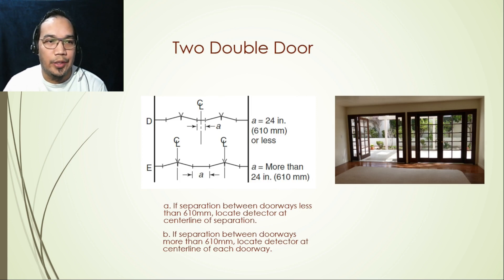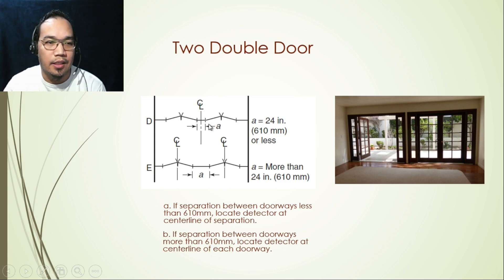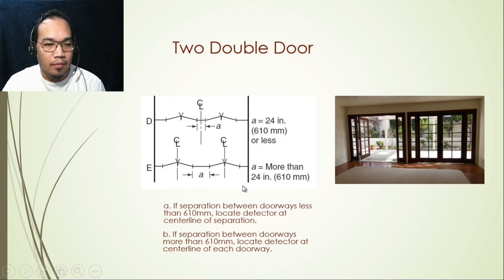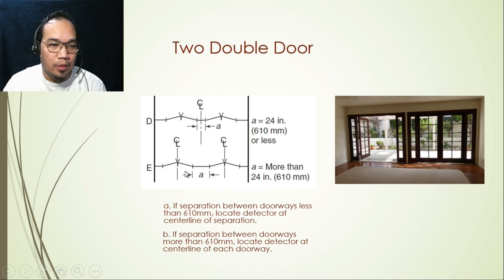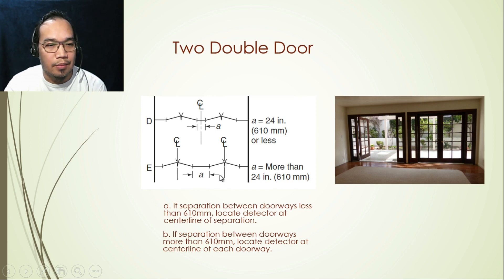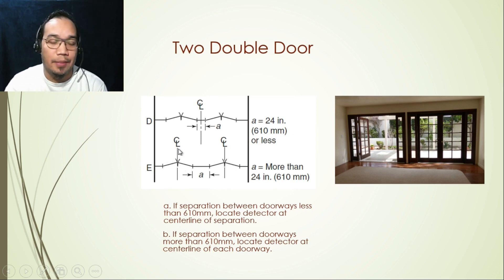If we have two sets of double doors, we measure the separation between the two doors. If the separation is less than 610 mm, we can locate one smoke detector at the center line of the separation. But if the separation between the two doors is more than 610 mm, we must consider a detector at each doorway, located at the center line of each doorway. So in that case, two detectors are required — one per doorway.